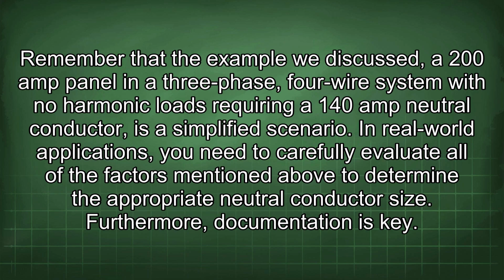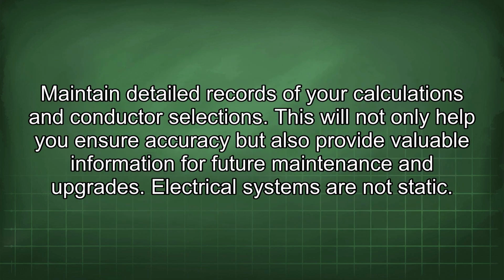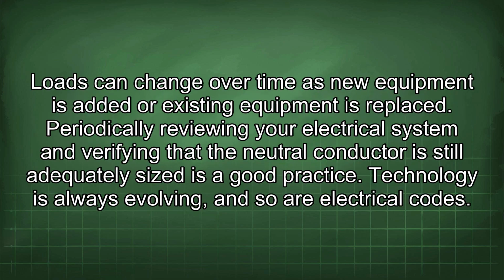In real-world applications, you need to carefully evaluate all of the factors mentioned above to determine the appropriate neutral conductor size. Furthermore, documentation is key. Maintain detailed records of your calculations and conductor selections. This will not only help you ensure accuracy, but also provide valuable information for future maintenance and upgrades. Electrical systems are not static. Loads can change over time as new equipment is added or existing equipment is replaced. Periodically reviewing your electrical system and verifying that the neutral conductor is still adequately sized is a good practice.